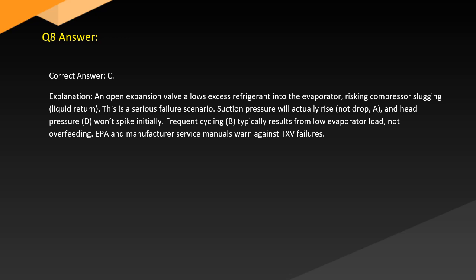Answer. Correct answer: C. Explanation: An open expansion valve allows excess refrigerant into the evaporator, risking compressor slugging, liquid return. This is a serious failure scenario. Suction pressure will actually rise, not drop, and head pressure, D, won't spike initially. Frequent cycling, B, typically results from low evaporator load, not overfeeding. EPA and manufacturer service manuals warn against TXV failures.